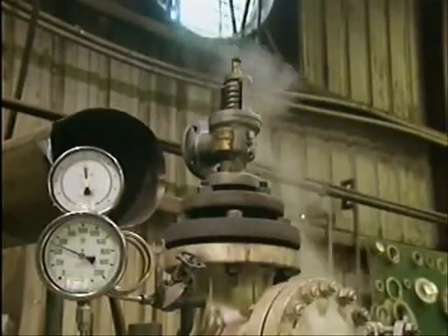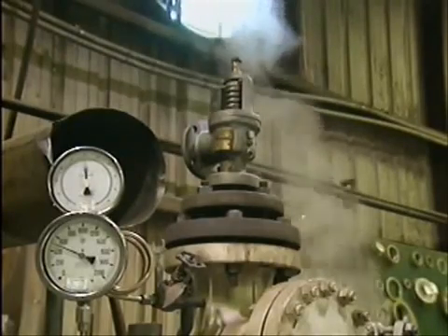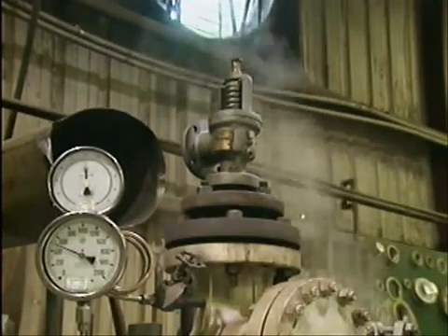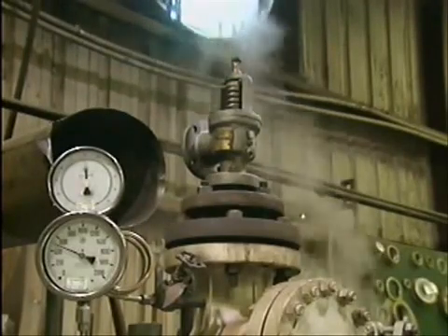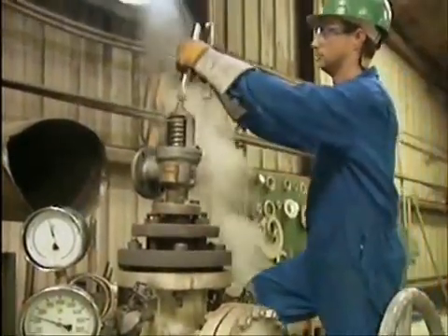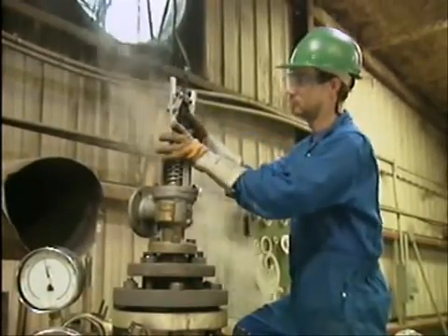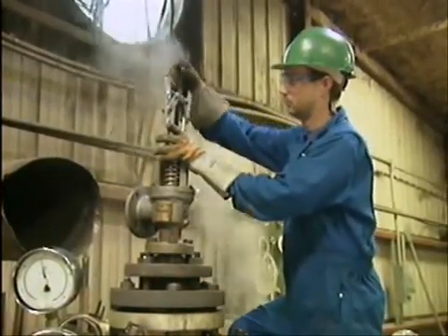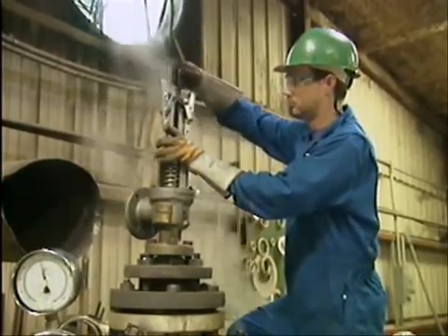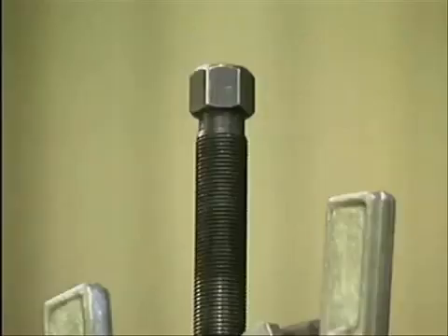We'll look at a typical procedure for installing a gag on a 2-ring huddling chamber safety valve. The valve's release lever and the protective cap have been removed, so the top of the valve stem is exposed. Now, align the stem of the gag properly with the valve stem. Then, attach the jaws of the gag firmly to the yoke to prevent the gag from slipping. Finally, tighten the gag finger tight only. Never use a wrench on a gag.